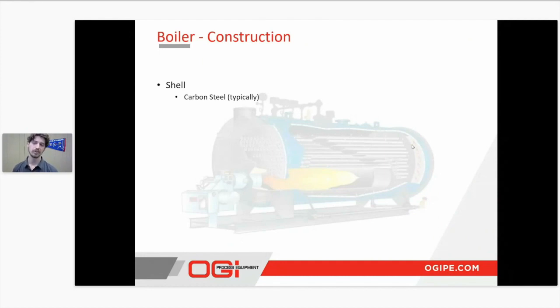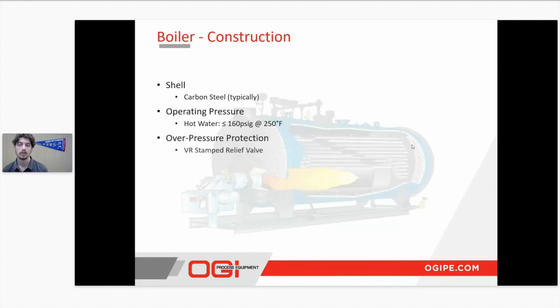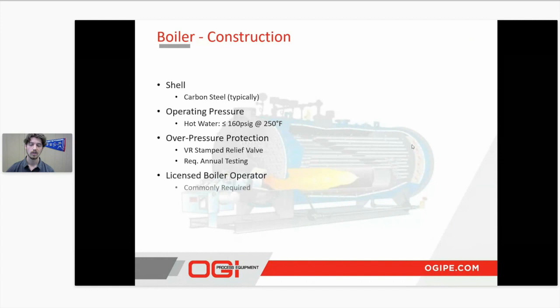Typically those are constructed with a carbon steel shell. The operating pressure is going to be about 160 psi for 250 degree Fahrenheit water. They tend to have a little bit of overpressure protection, being a VR stamped relief valve, and required annual testing and repair for these units. As well, it's very common for most states and large cities to have a licensed boiler operator required to be working on these units.